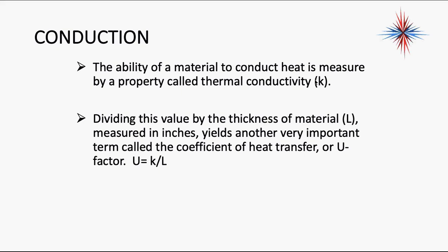The ability of a material to conduct heat is measured by the property thermal conductivity. You divide that value by the thickness of the material measured in inches, and it yields another important term called the coefficient of heat transfer. This is where we start talking about some of what you're going to be doing on your design. We are going to use the U factor for everything.